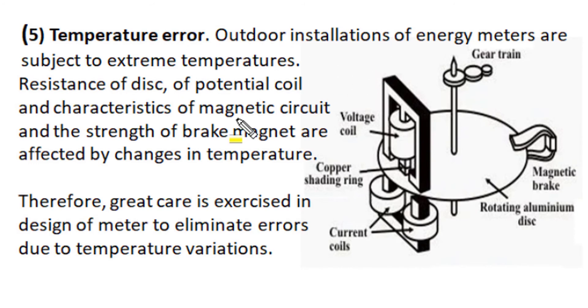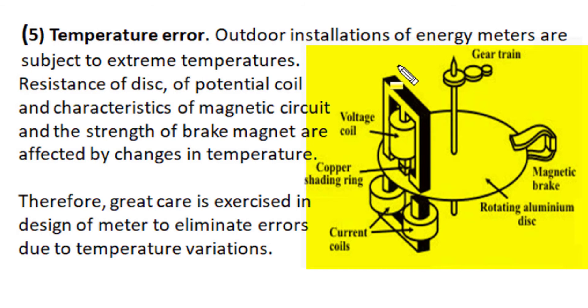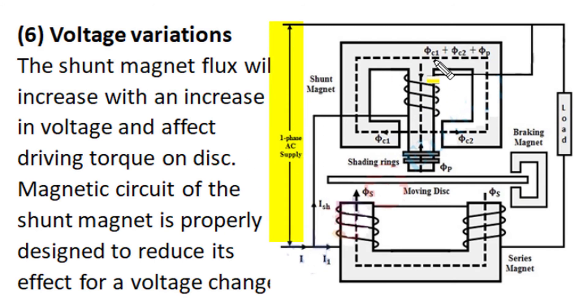Energy meters installed in outdoor locations are subjected to extreme temperature variation, which can cause considerable error. Temperature changes can alter the resistance of the disk, resistance of the voltage coil, magnetic characteristics of the magnetic circuit, or strength of the brake magnet — all affecting driving torque and braking torque on the rotating disk. Some of these effects partially cancel each other. Appropriate care in design and material selection is taken to eliminate errors caused by temperature variation. Variation in supply voltage magnitude can also change the current in the shunt coil and flux of the shunt magnet, affecting driving torque and measurement accuracy.